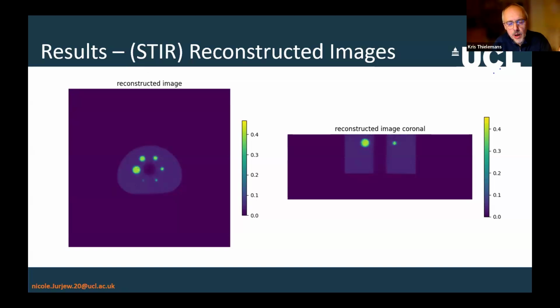Exactly how many you need depends on your voxel size and the ratio between the voxel size and the bin size and things like that. But we use something like 5 or 10, which tends to give much better results. It also implies you have some resolution modeling as part of the ray tracing projector if you use multiple lines.